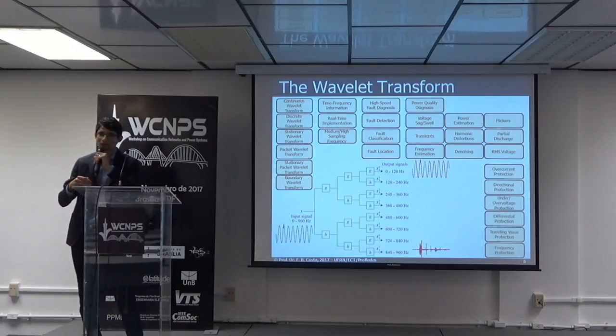So it's a very new application, and there are some technological problems, and solutions are appearing every day to solve these problems. But the way to get the information is one of the main concerns, because if the transducer doesn't respond to a high sampling frequency, if the high frequency is filtered, you cannot detect the traveling waves successfully.